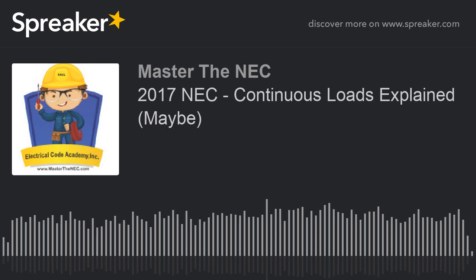So we take the 20 amp rating of the device and you divide that by 125%. That is 16 amperes. Okay? So 16 amperes is the maximum continuous load. And remember what I said at the beginning? The load is the load, okay? 16 amps started out as a load. If it's a continuous load, it's still 16 amps. You just treat it as a continuous load.